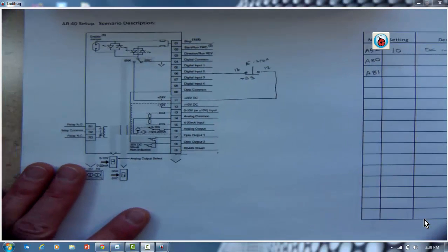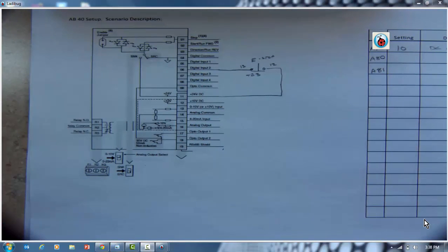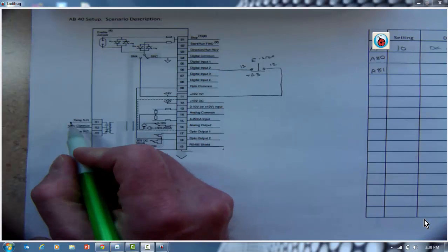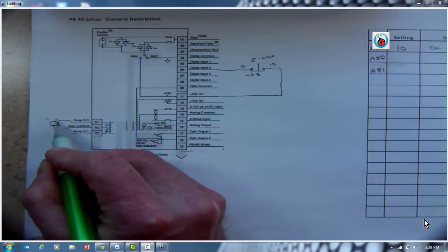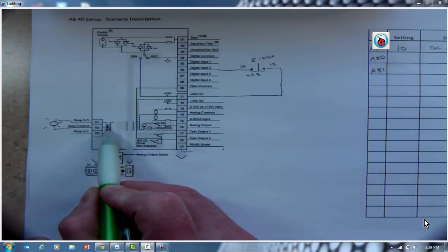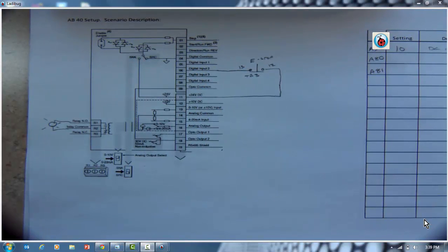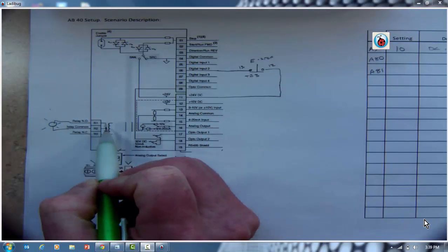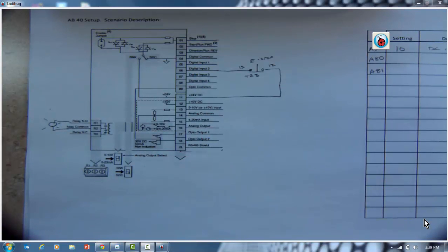Now, down here on the relay, that's another piece that's going to have to be wired in. And you're going to have to remember how to wire in a relay. Remember, you can hook a light up to this all day long, and nothing will happen. That really is just a dry switch. There's no power on it. You need to bring power to the light, through the light, and use the switch, right? So typically you'll bring negative or a grounded conductor to the light, and then you'll bring positive through the contacts. So that's going to be a little memory game for you as well.